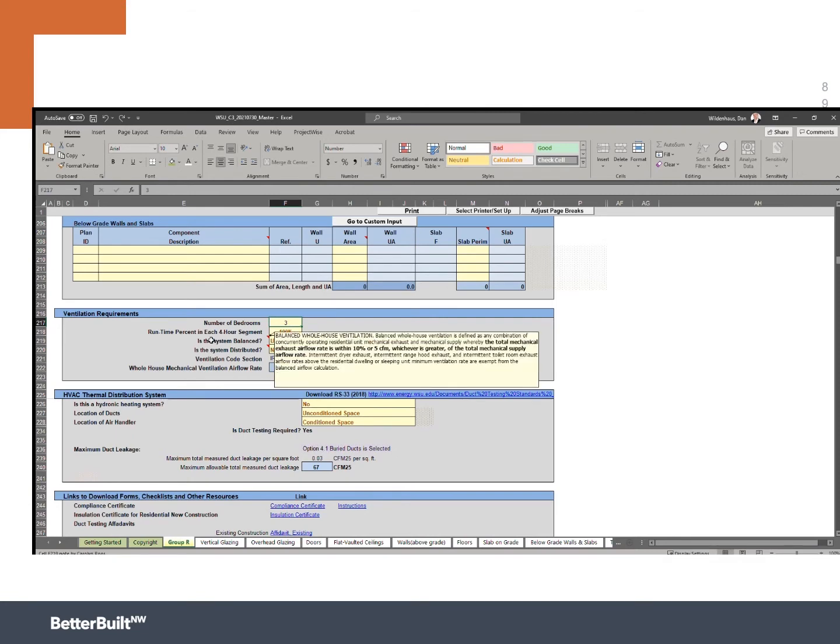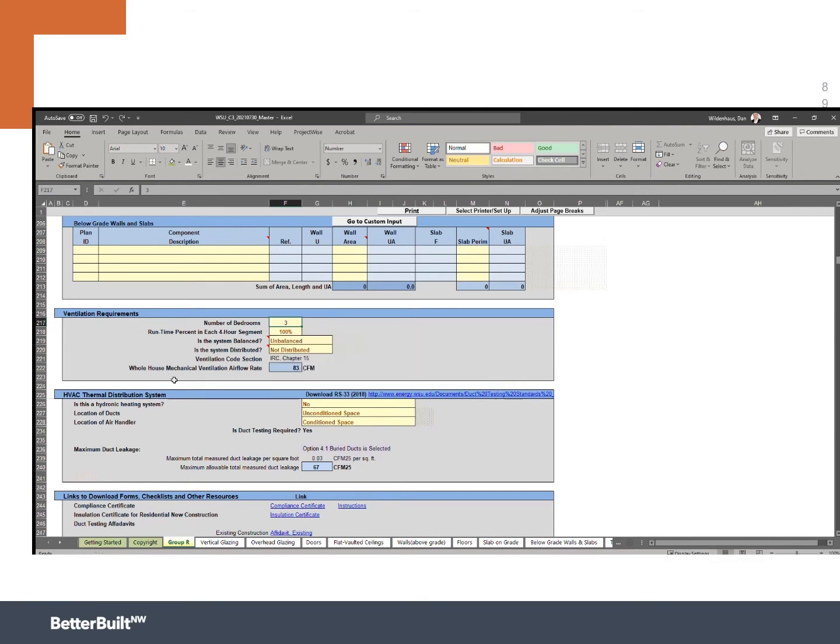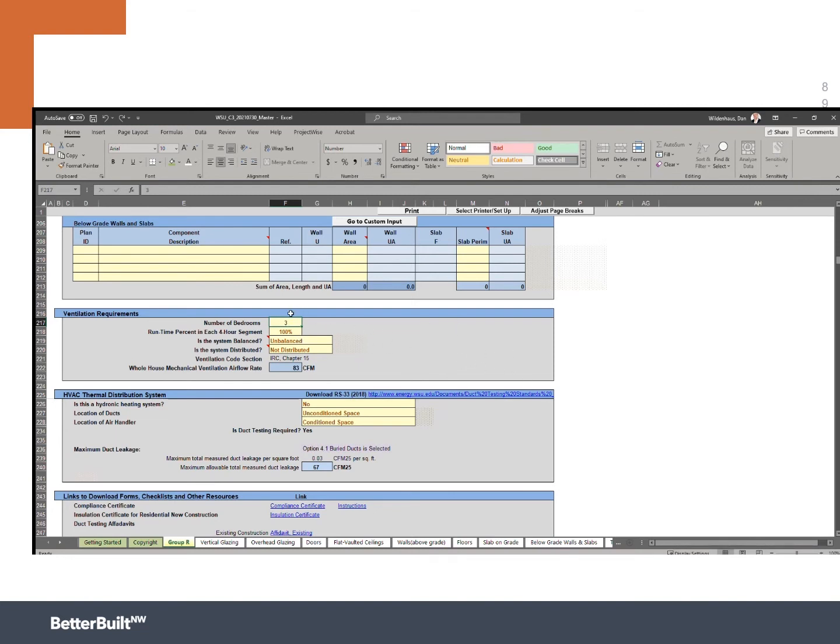Effectively, balanced means the same amount of air is being pushed into the house as being sucked out. And distributed means you're actually delivering this fresh air to all the livable spaces of the home. So based on that size house, 2,222 square feet and three bedrooms, if I used an exhaust fan and I let it run all the time, I would need 83 cubic feet per minute in order to achieve this. So maybe I purchase a 90 CFM exhaust fan and I let that thing run all the time.